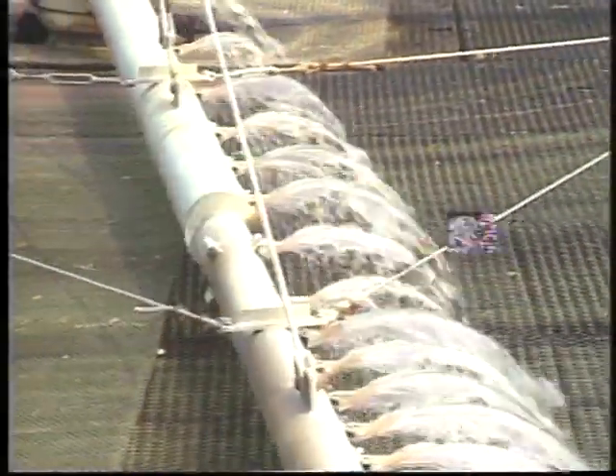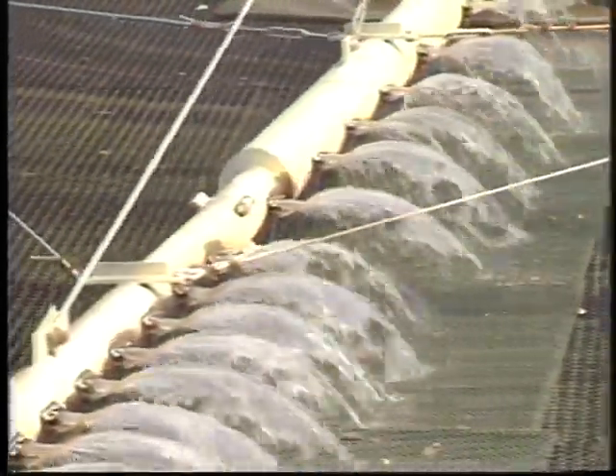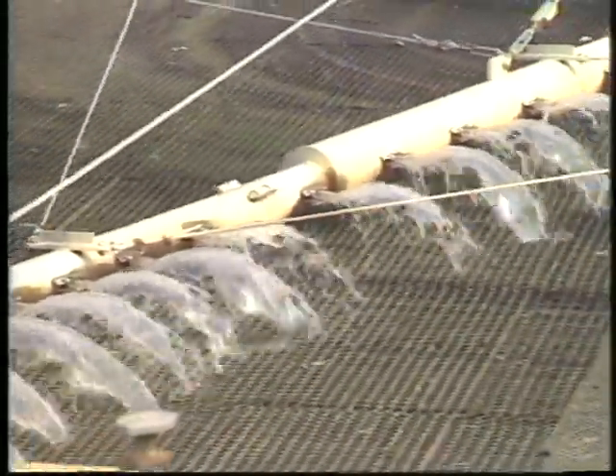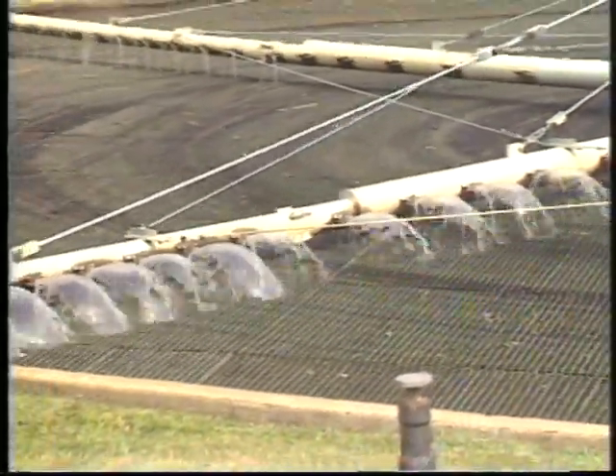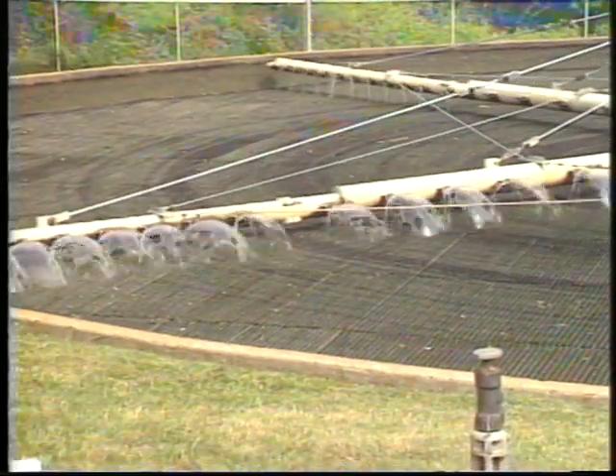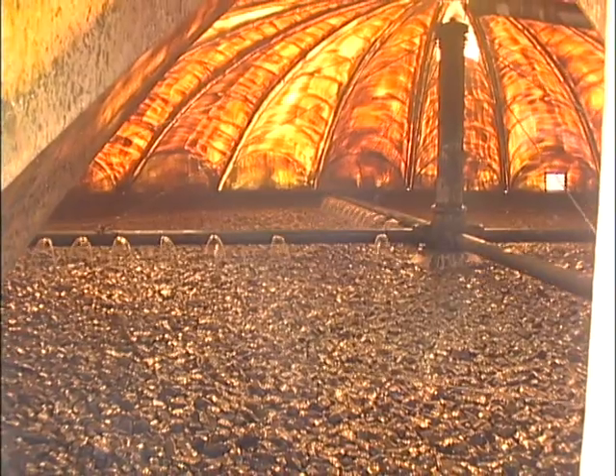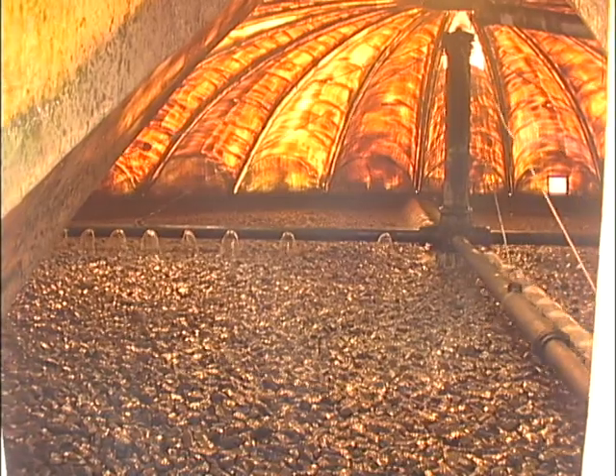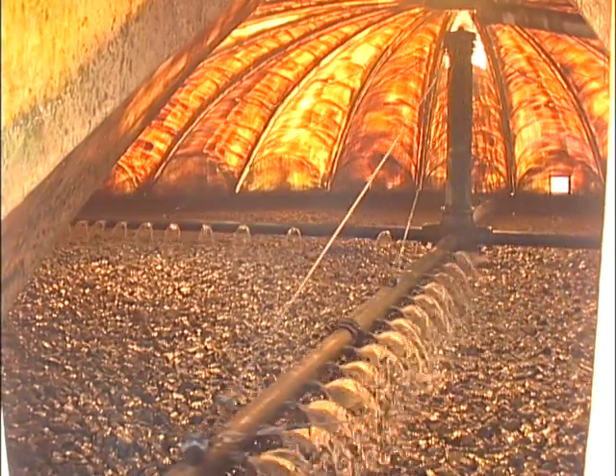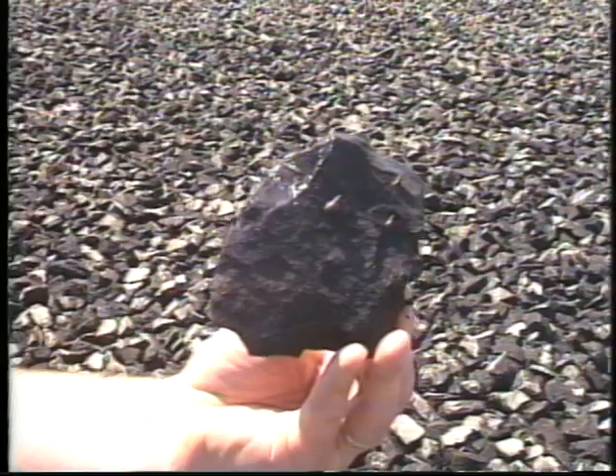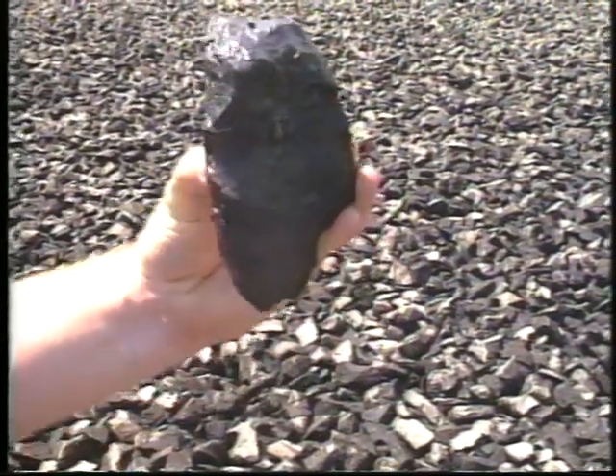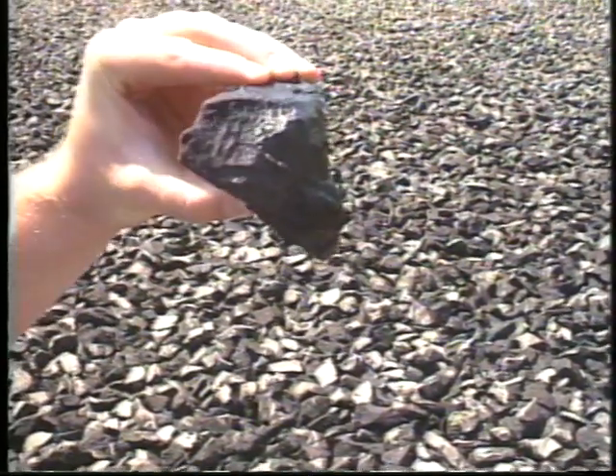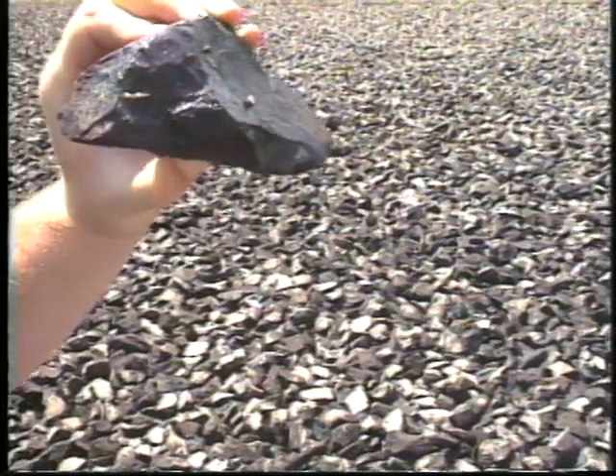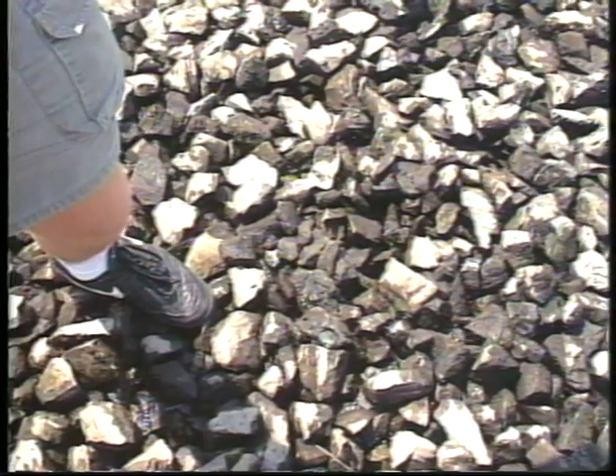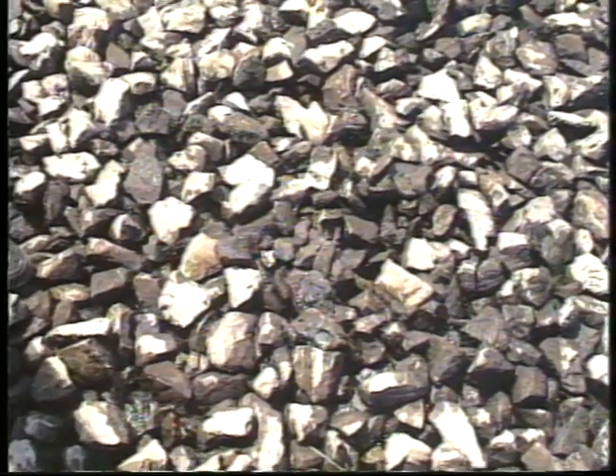The media provides surface area for microorganisms to grow and feed on the organic matter in the wastewater. In all trickling filters, the media is either a stacked type or random dump type of media, such as rock. Random dump media should be uniform in size to facilitate airflow through the media. As the name suggests, this media is dumped into the filter up to the desired depth. Random dump media may also be made of plastic or other materials.